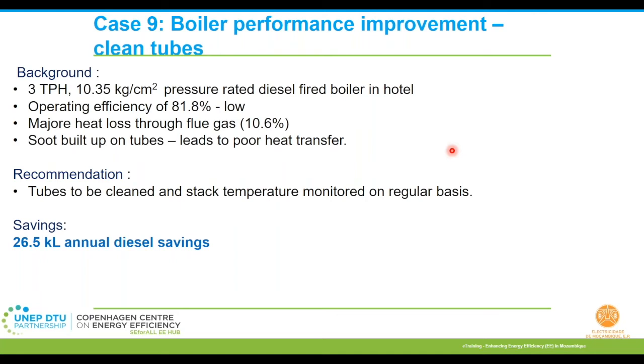This was done through the indirect method, so you will have different components of losses also calculated through indirect methods. We have identified that almost 10.6% of the heat loss was through flue gas losses. For the investigation, we identified that the boiler tubes, the heat exchange tubes, had soot built up on the surface. Due to this, there was poor heat transfer happening, and since the entire heat could not be absorbed to generate hot water, the heat was being lost with the flue gas.